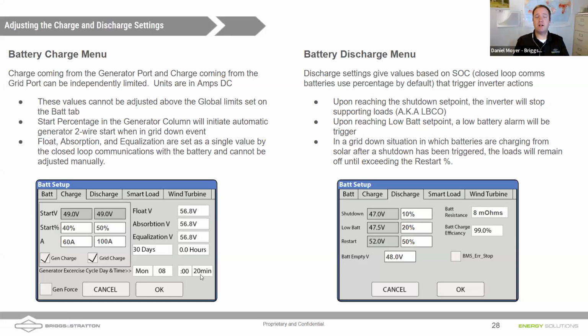So Nathan, yep, just ahead, talked about doing the charge. Now, let's assume that you are off-grid, and that's what essentially whole home backup is. If the batteries start to run low, certain things are going to start to happen. You can adjust what's known as the low battery setting, and these are based on state of charge of the battery. Once it reaches, in this example, we have it set to 20%, an alarm is going to start to go off. You're then continuing to discharge the batteries. At some point, in this example, we have 10% of the battery's remaining capacity. We're going to shut down.